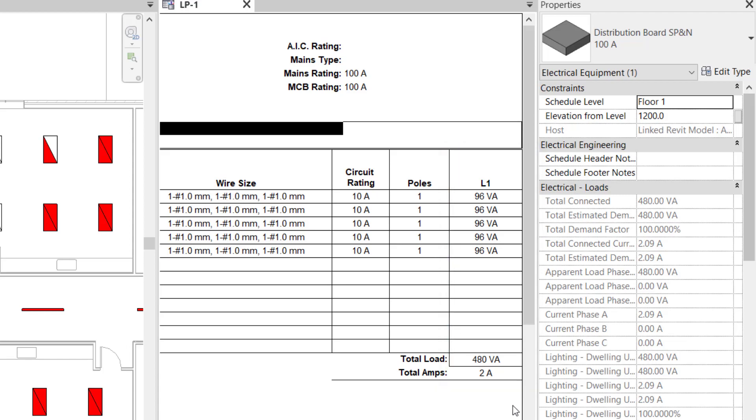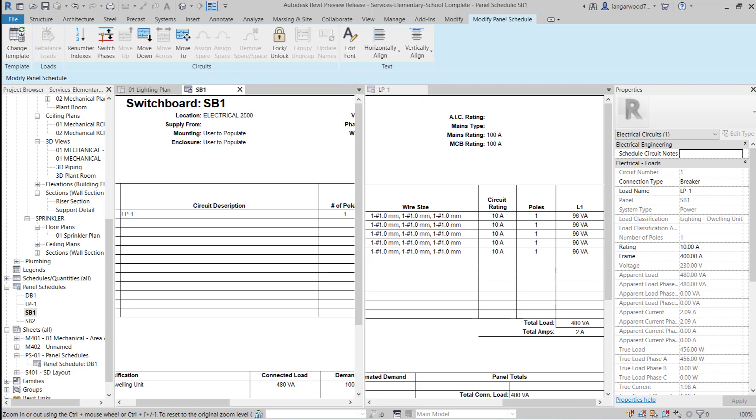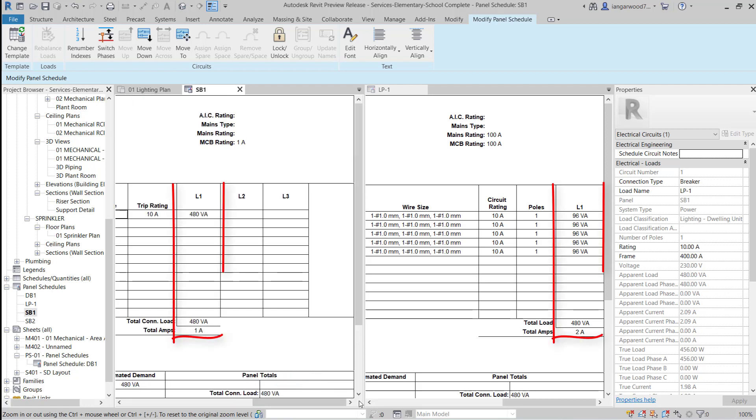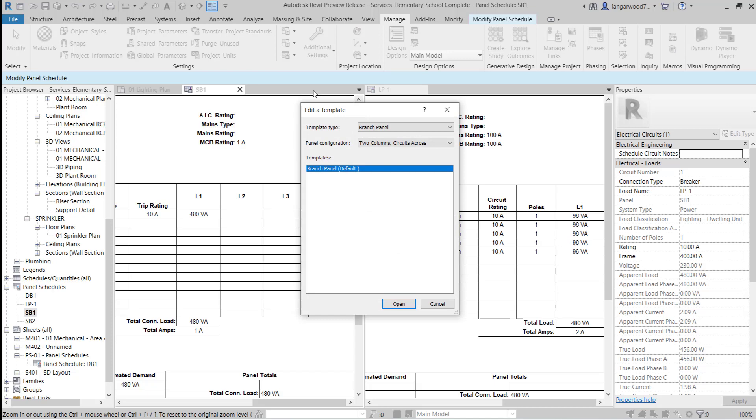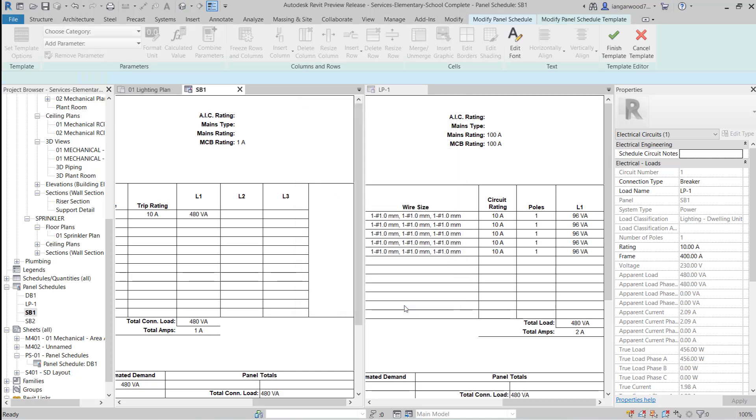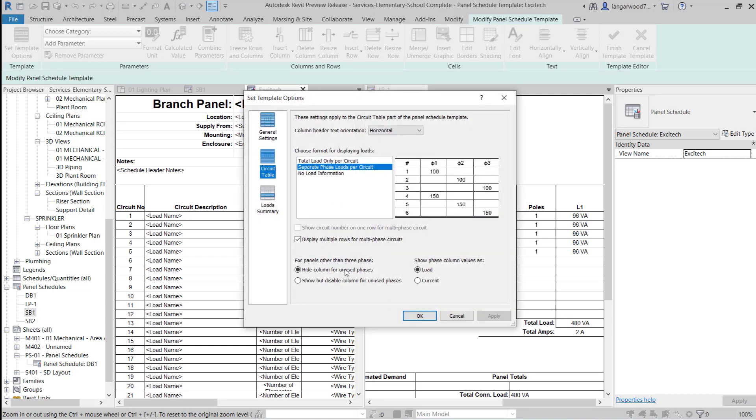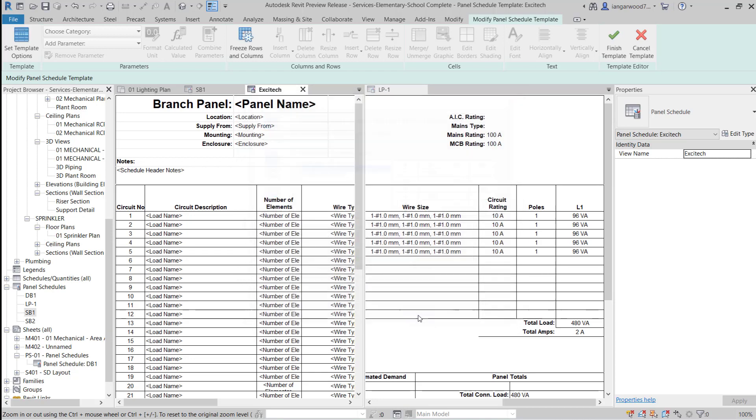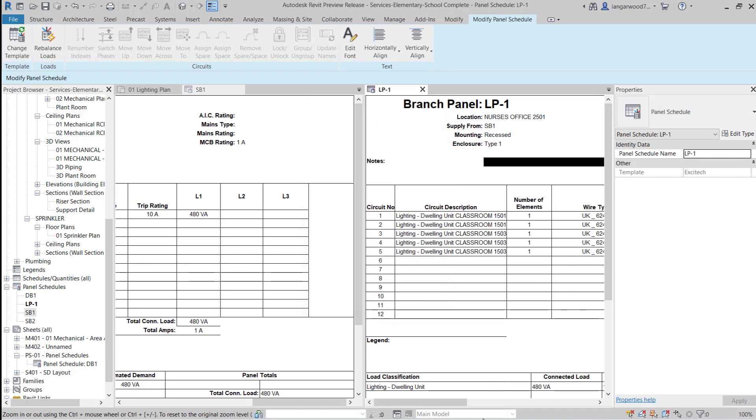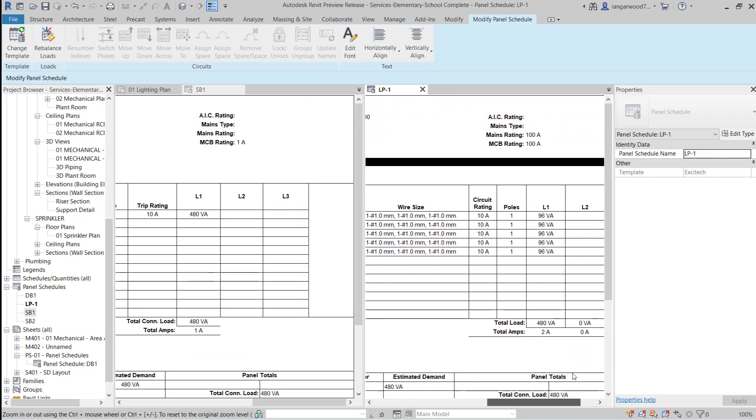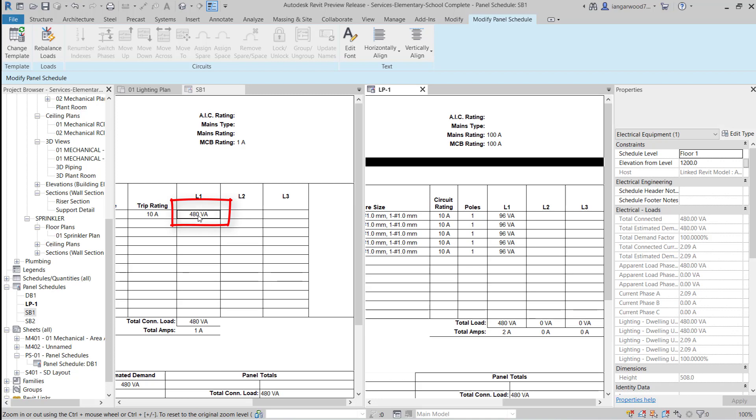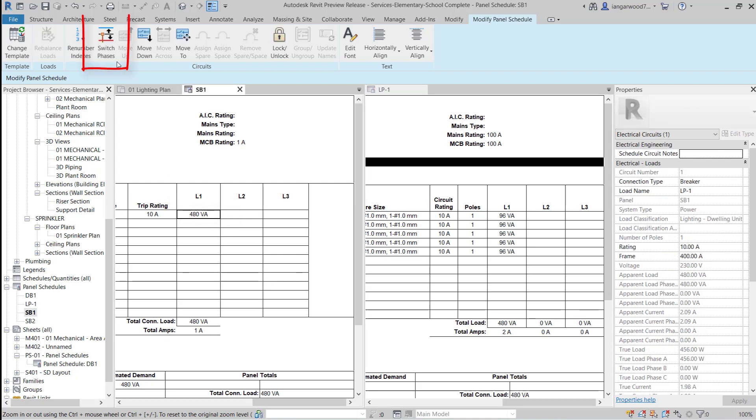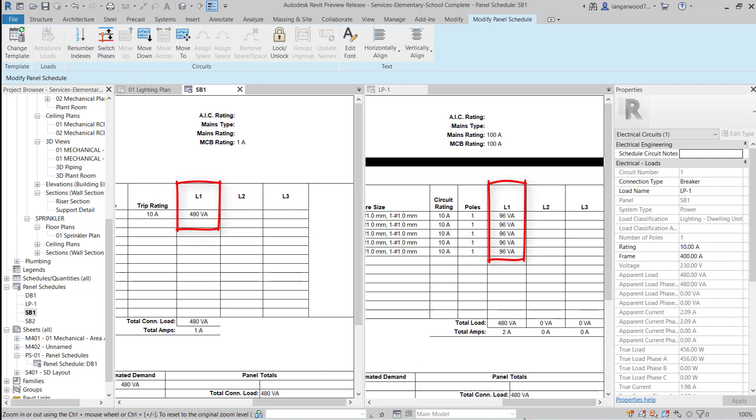Let's now take a look at the two panels we've been working with, LP1 and SB1. We can see that the loads for LP1 are totaled on the switchboard SB1 and the LP1 is connected to the first phase of SB1. We have already seen that we can use the new switch phases feature to change the connected phase for single phase panel boards on a switchboard. So I'm going to edit the panel schedule template as before to change the display of the single phase panel schedule so that it shows the three phases. If we now turn our attention to the switchboard panel schedule for SB1 and select the circuit for LP1, we can use the switch phase feature to move the circuit to different phases. At the same time, we can see that the single phase panel board LP1 is updating to reflect that change.